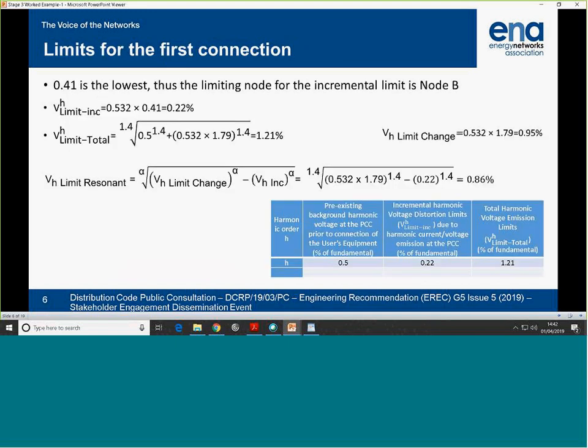Then I multiply 0.532 by the background, the smallest term. That is my limit for connection 1, the incremental limit for connection 1. I don't use any data from the customer. Then the total limit: at station X, where the connection is made, the headroom there was 1.79, and that's my total limit, 1.21.